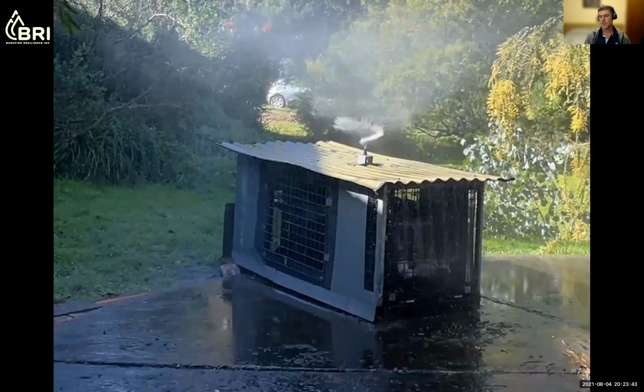What spray systems won't do is prevent embers getting to and being ingested by the pump. We see time and again that spraying water around simply doesn't stop the ember storm - the embers don't go out because there's water around. There are so many embers you just cannot rely on spray systems to keep them out of the enclosure, and internally that enclosure will be dry for the same reason your roof or wall cavities are dry.